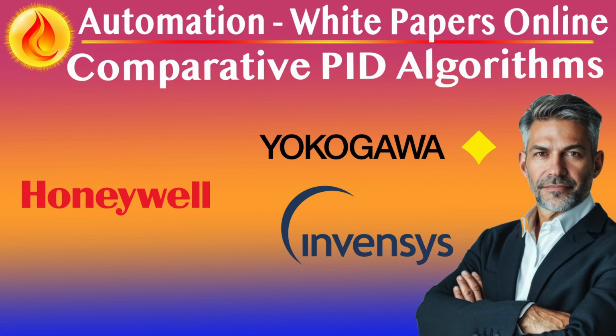Invensys applies derivative to error in its series algorithm by default. Without filtering, this can cause excessive reactivity and jitter in loops with noise or operator-initiated setpoint changes. While filtering is possible, it may require extra configuration and, in older systems, must be added via separate blocks. Later Invensys platforms introduced derivative on PV options and built-in filtering, but these enhancements are platform-specific and may not be uniformly implemented across legacy assets.